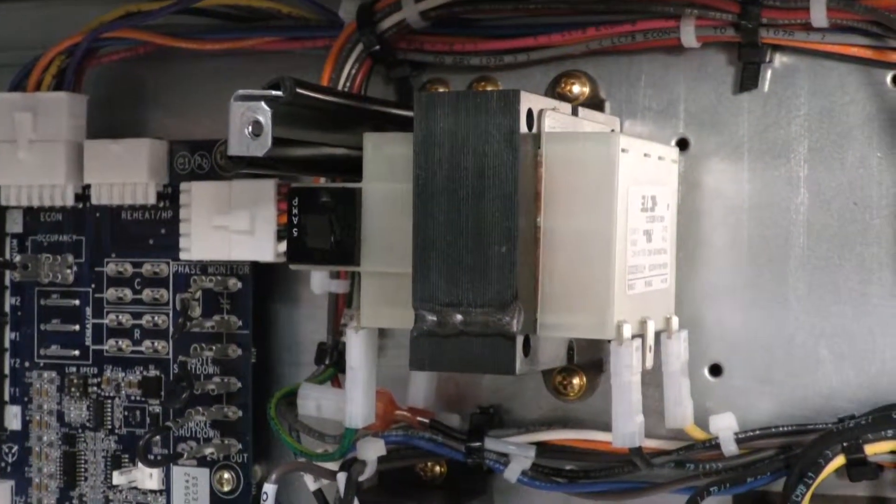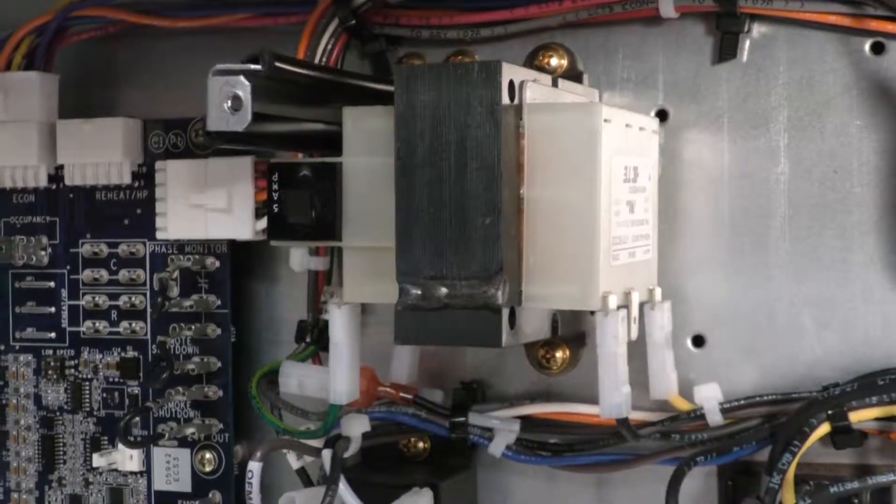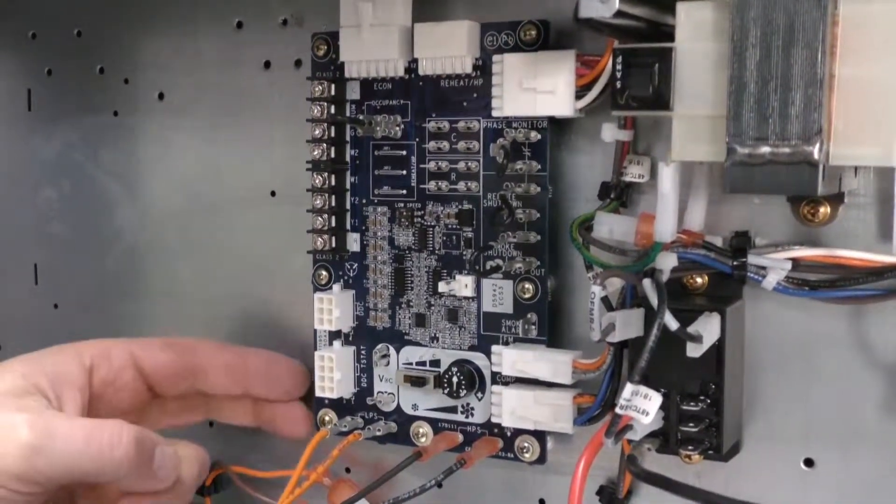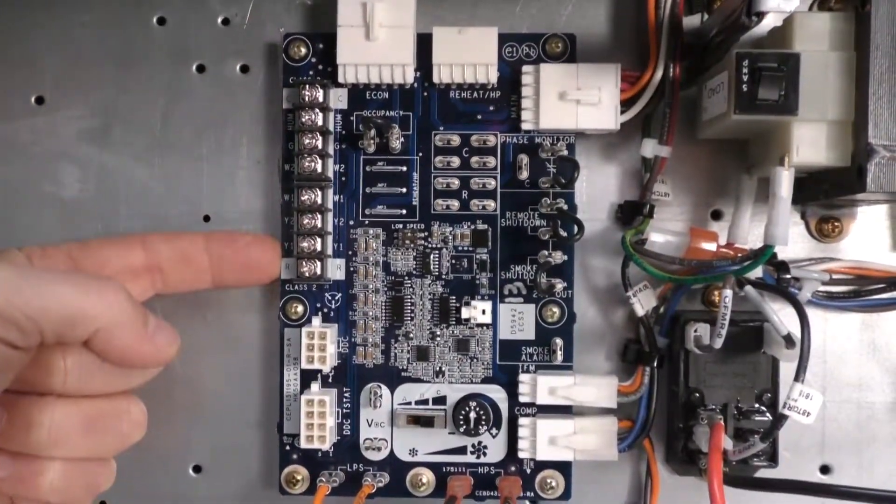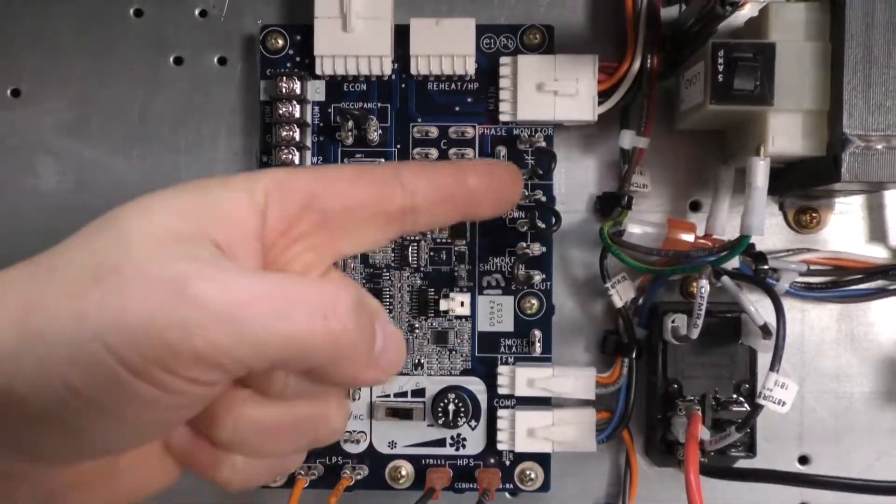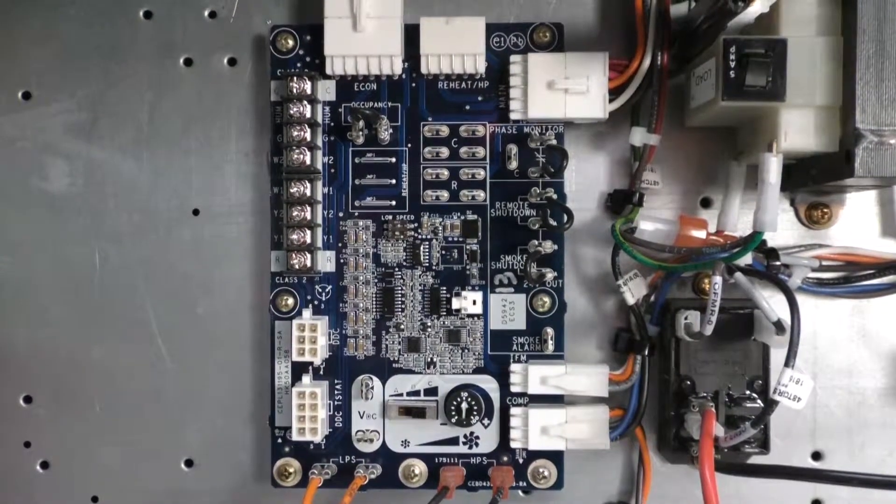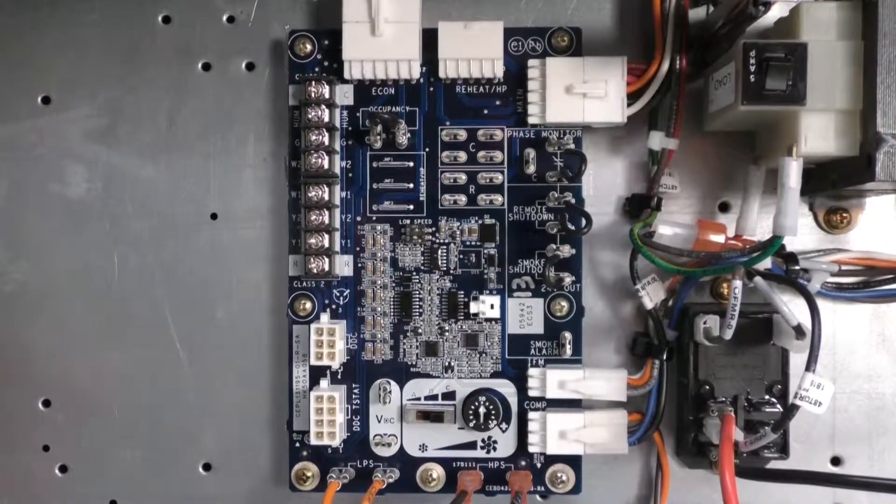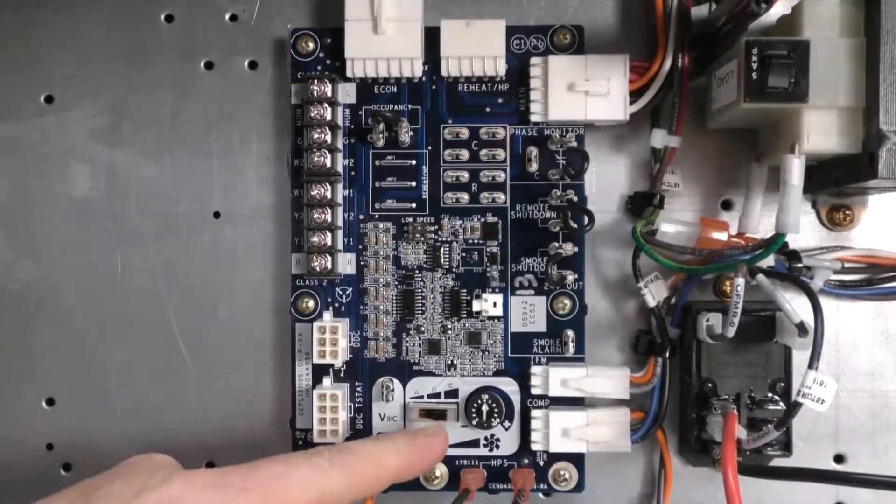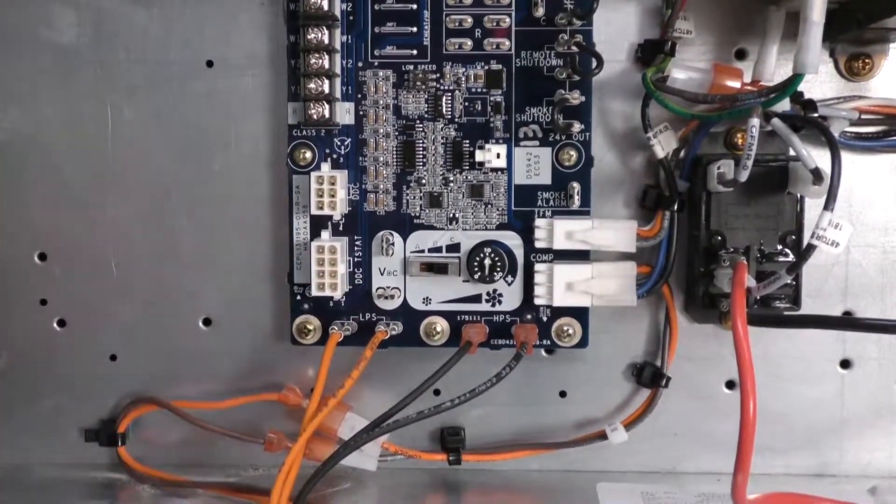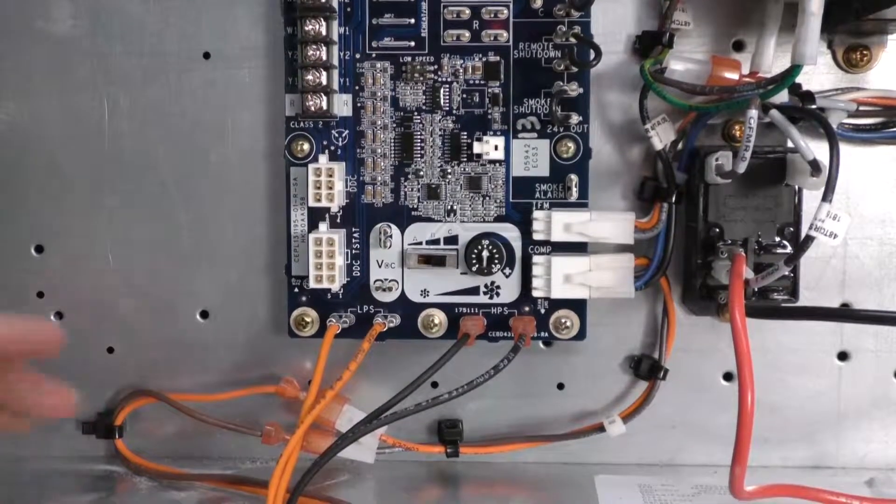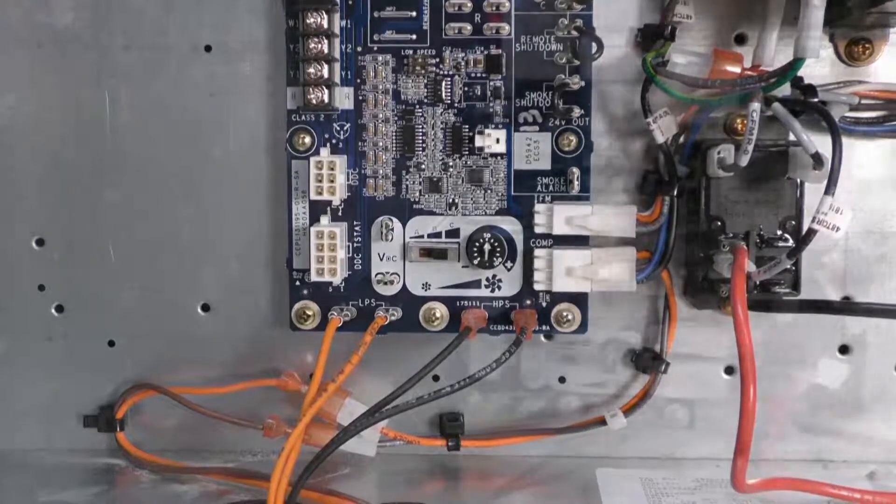Our control voltage transformer and our new fan control board. This fan control board is not much different wiring wise than the existing one. We've got our low voltage connection for a low voltage indoor thermostat. Our jumper wire connections for things like occupancy control, smoke control. What is a little bit different about this particular board is the fact that at the lower portion of it, as we'll see later, there is a way that we're going to set up the air flow for the indoor fan. It's a different procedure, as reflected on the label on the outer panel.